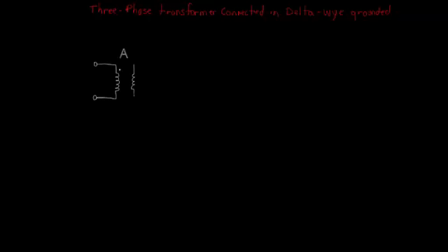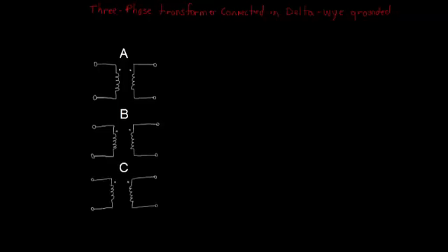Now, let's explore some three-phase transformers. There are two options to define a three-phase transformer. The first one consists in the connection of three single-phase transformers, and the second one consists in declaring a single three-phase transformer. For example, suppose that we would like to define a three-phase delta Y-grounded transformer by using the first method. Then we should define three single-phase transformers, which will be called A, B, and C.